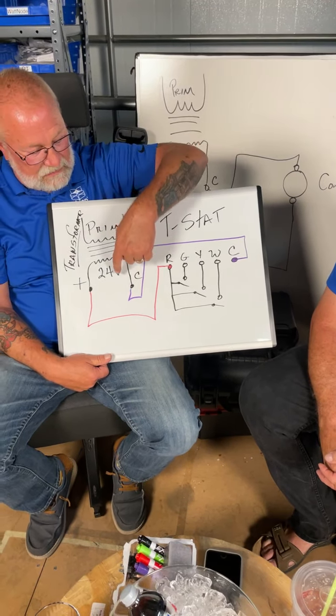the past few days, a young man was reading from one side of the contactor coil to ground, and he says, I got 24 volts there, and then I go to the other side of the contactor coil, and I got 24 volts to ground. So I got 24 volts going through the contactor coil. Right. Well, no, you really don't.